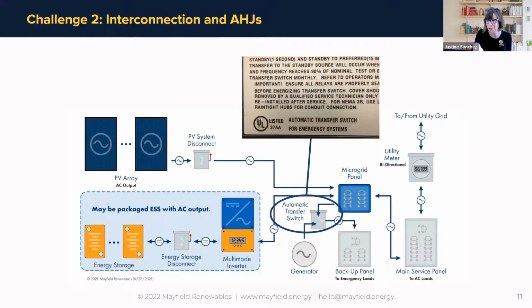If you look here, we have our microgrid panel. You see your PV array; we're not showing the individual string inverters in this case, just assume there's an AC output. It feeds our microgrid panel. Also feeding our microgrid panel is our energy storage system: the output of our battery inverter feeds it. And then our utility connection feeds the microgrid panel. Those items are what's connected to the normal side of the automatic transfer switch. Under normal operation, that emergency panel, and there's actually another panel not shown here, the optional standby panel, is being fed by our microgrid panel.